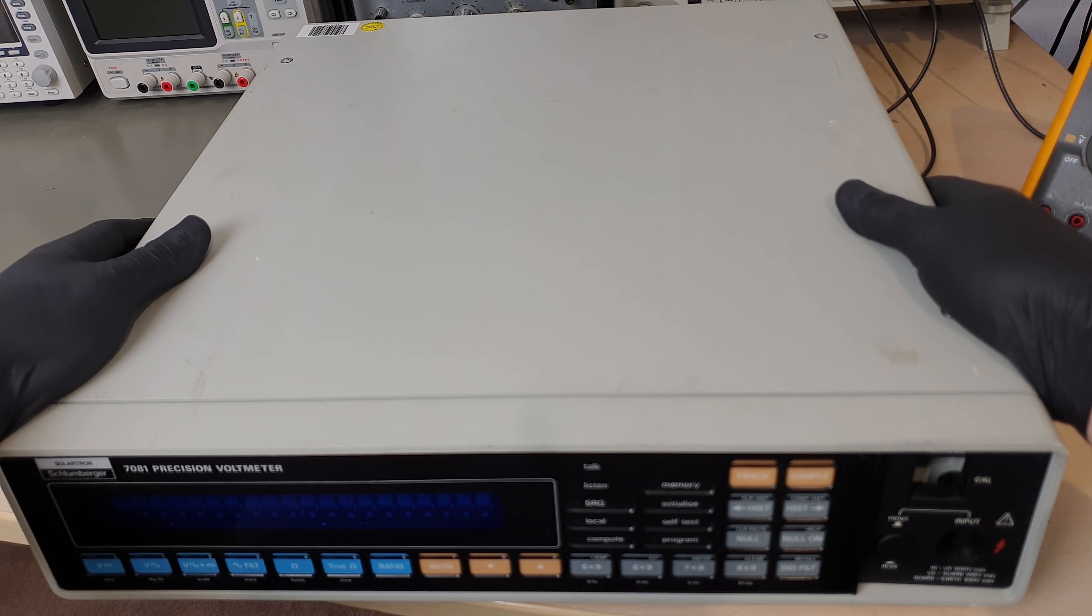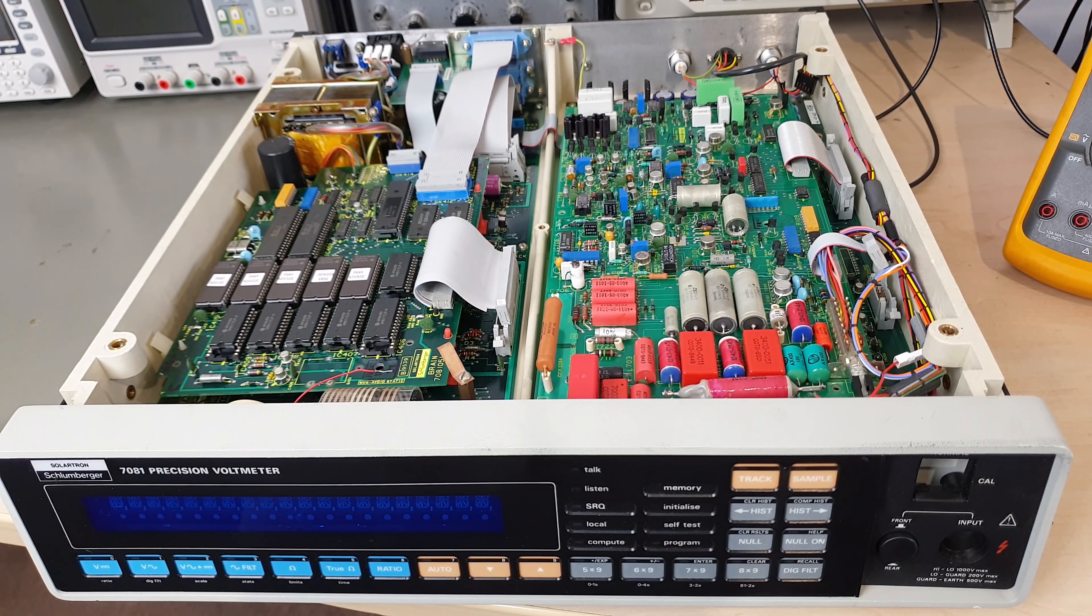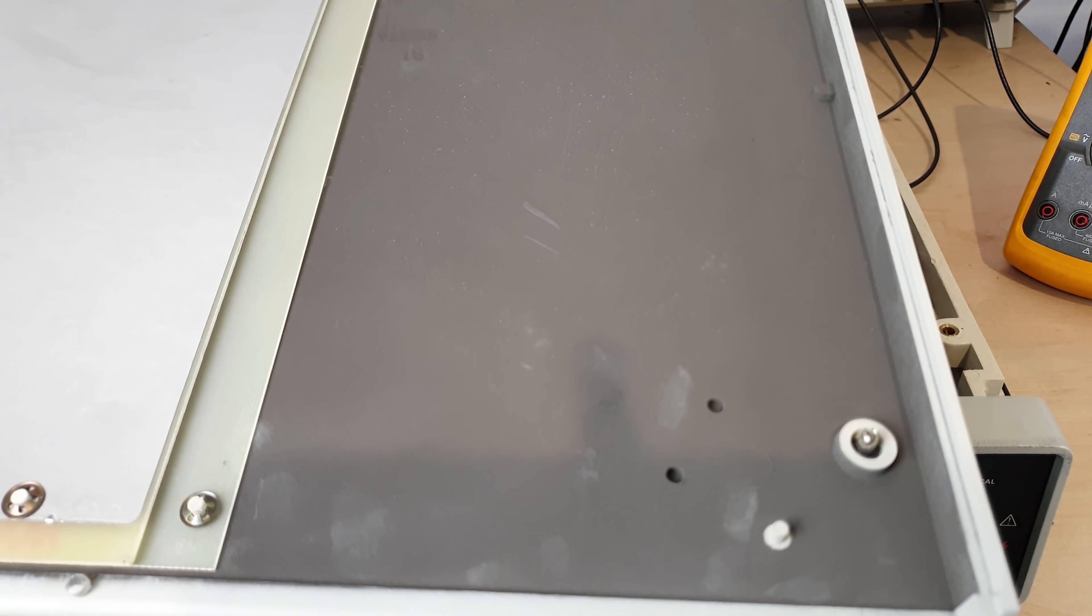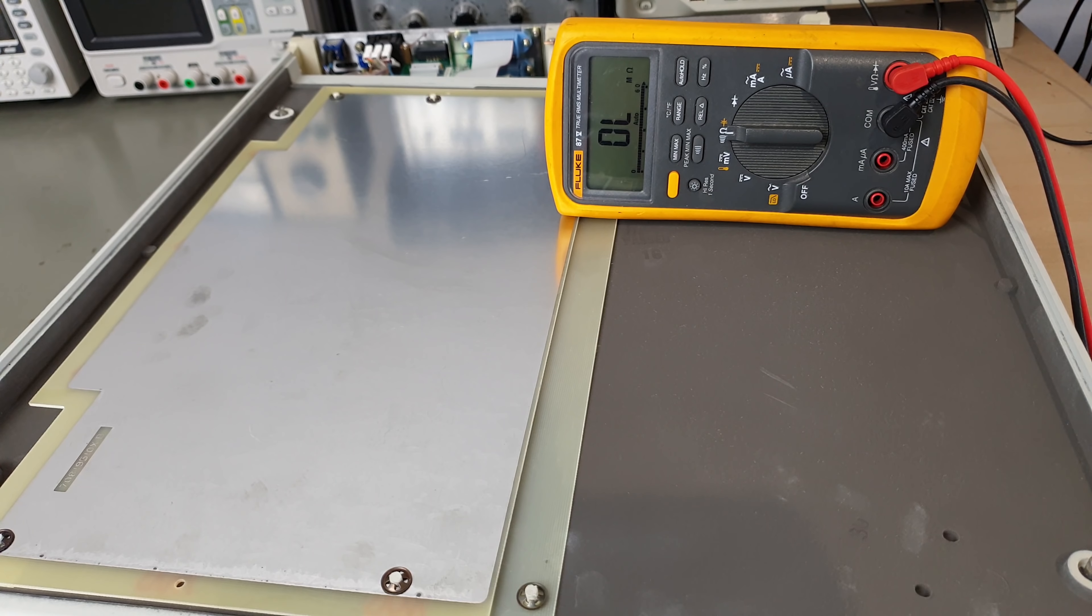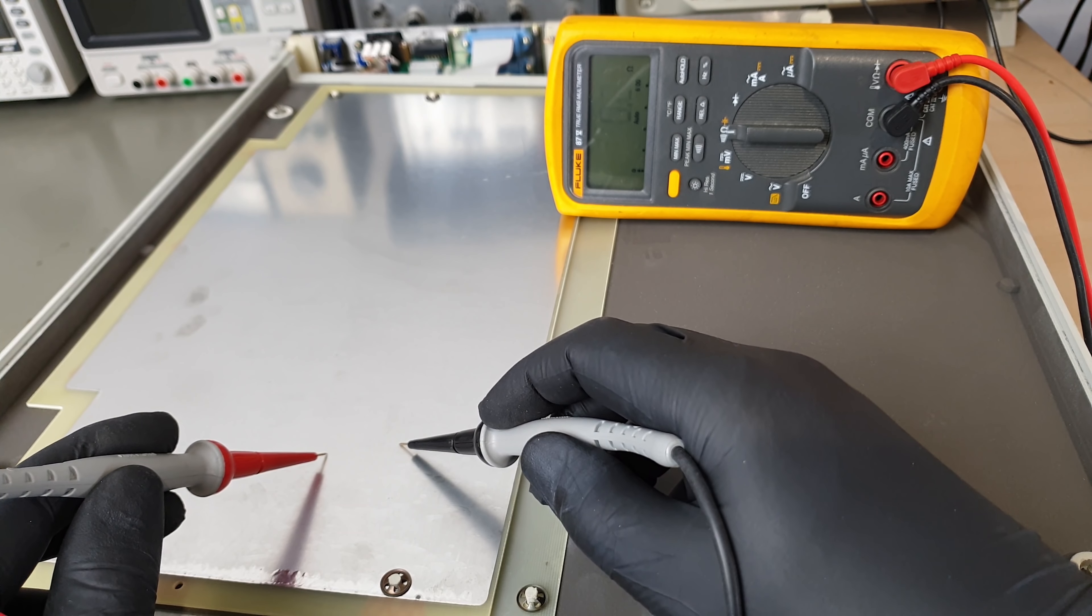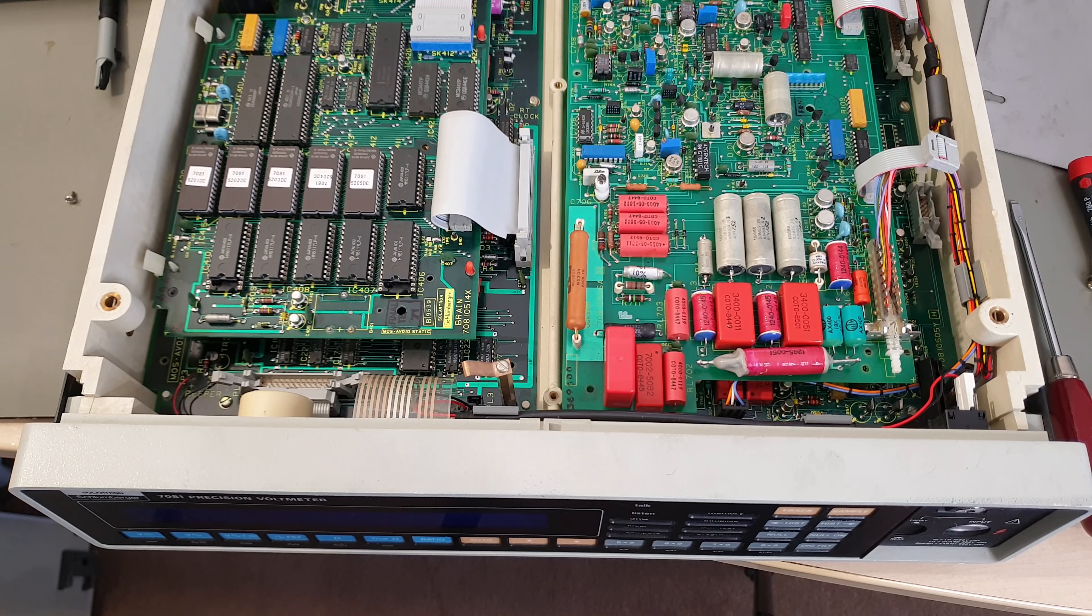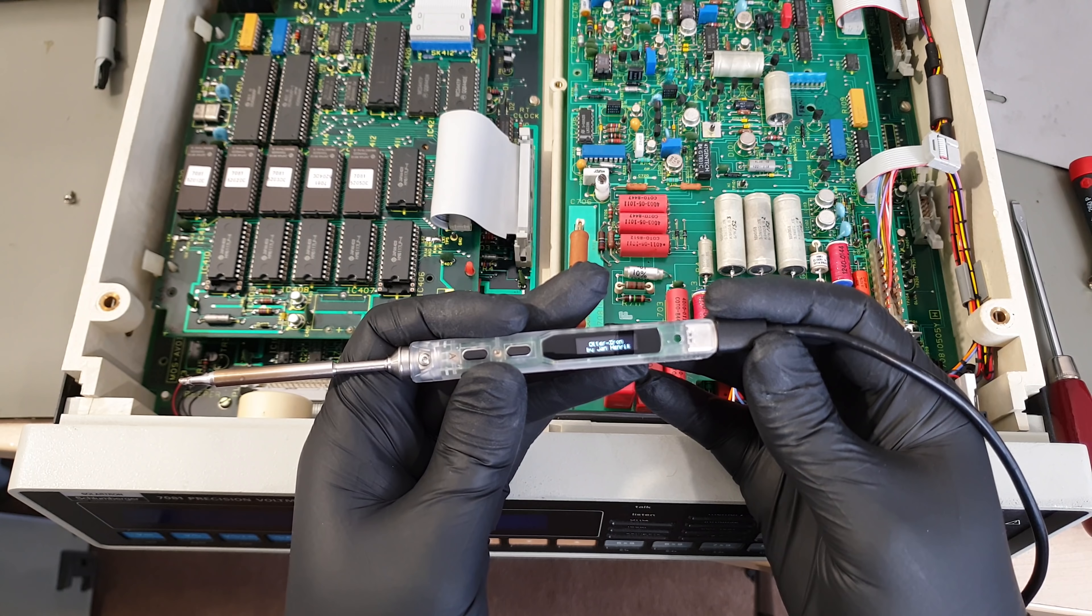First of all, it's not a big deal. These are not first world problems, these are absolutely esoteric ivory tower problems. So no hard feelings towards this absolutely esoteric ivory tower voltmeter that somehow managed to be this awesome in the 1980s. I love the enclosure, even though it's not metal. I think this thick fiber reinforced molded plastic provides better thermal insulation for the insides than sheet metal could. It also doesn't have grills or even cooling fans further improving thermal stability and letting absolutely no dust in. The lid is coated conductively and connected to mains earth when closed. That doesn't seem to be enough because for the sensitive analog area there's an extra shielding PCB that gets connected to a floating guard node. The front panel is a piece of art, absolutely no sign of yellowing in the high quality plastic. And have you ever seen a foil membrane keypad that still works like new after 40 years? It's a miracle.